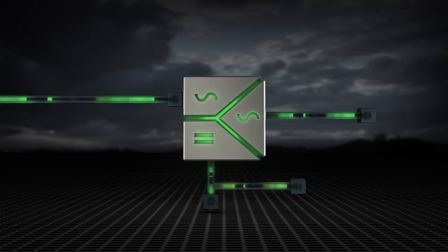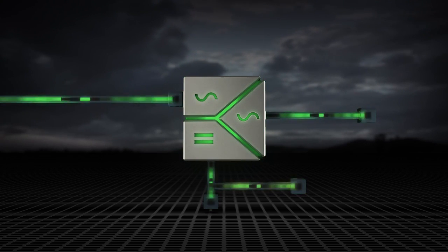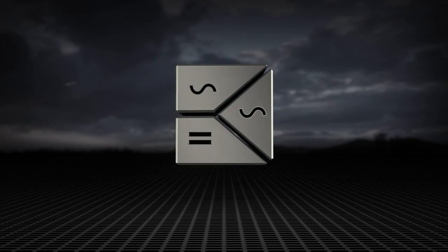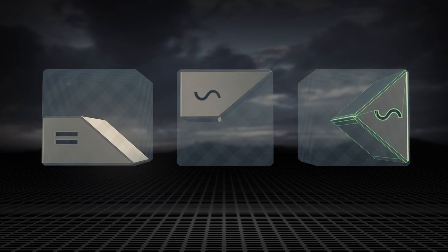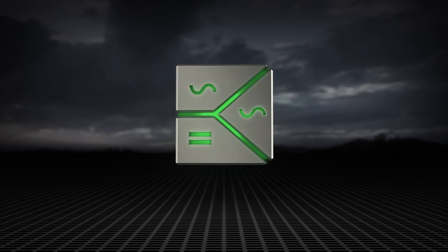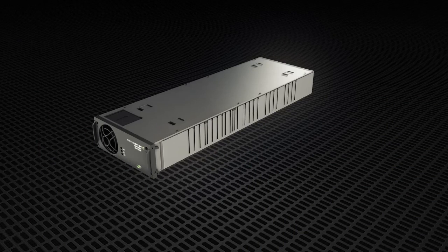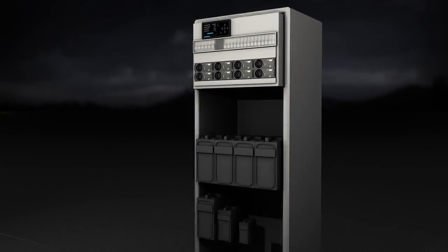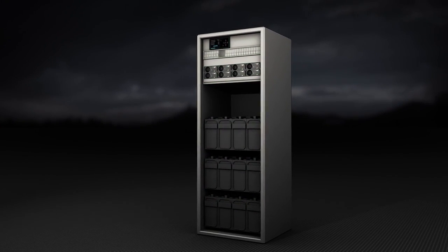It's also modular in this transfer technology from DC to AC feed, which means that this transfer is also in redundancy. It's not a kind of static switch that could be a single point of failure. When investing into systems like this, usually you have invested in a rectifier system and an inverter system with probably from 2 different suppliers with different controllers. Now you have it in one box with a much simpler solution, one controller. So of course your cost of ownership will be reduced.